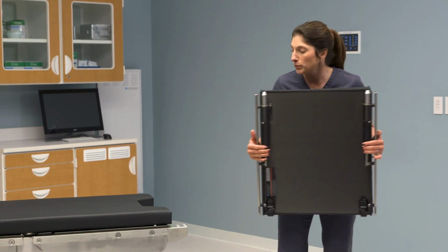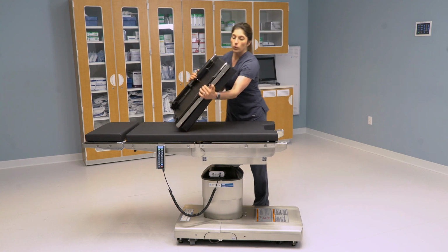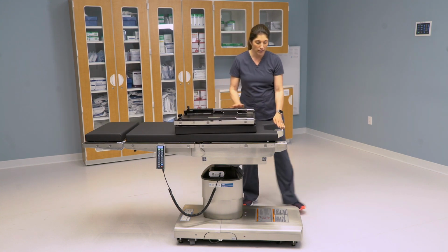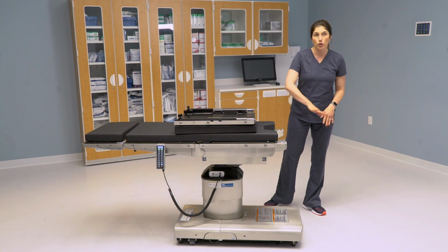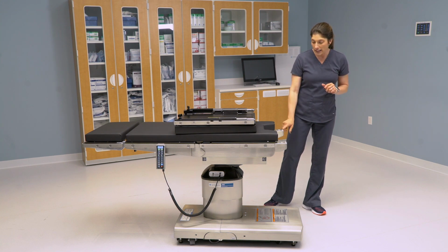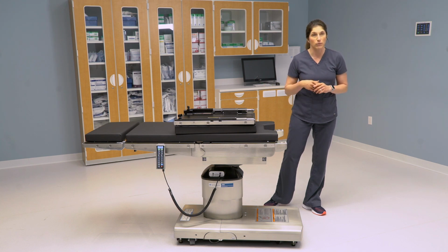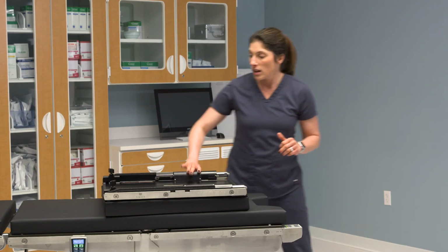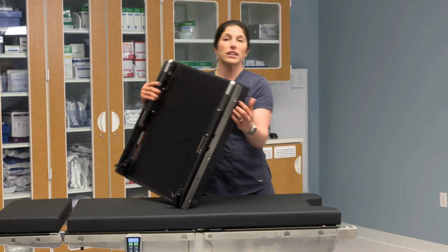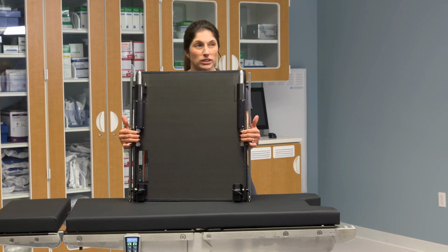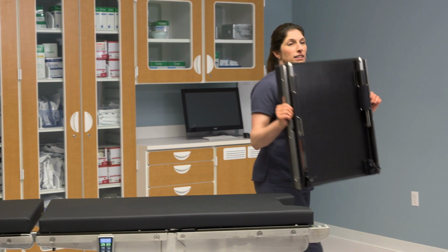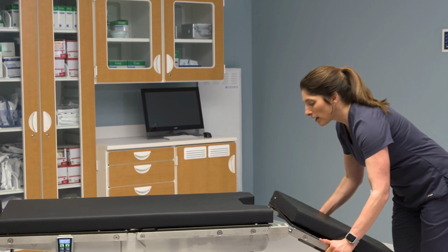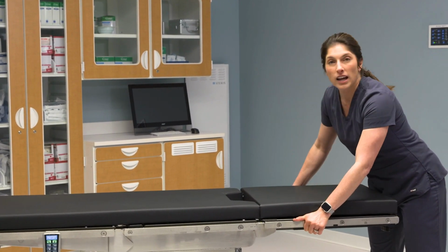But before we do that, let me show you one other thing. When you remove the leg section, you have the ability with the hand control to lower the leg section and get the receptacles tucked in and out of the way. And when the receptacles are tucked in and out of the way, you can get full slide of the table to head and to foot. So if we're going to reapply the leg section, no need to hold these levers to do it. You just take the leg section, line it up, and insert it.